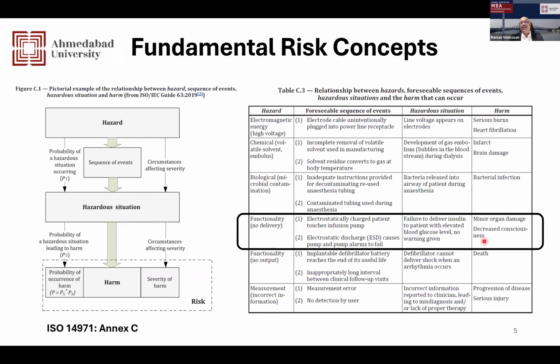And if that hazard somehow were to happen in a harm, the harm will probably be a minor organ damage or a decreased consciousness, which is a localized effect. But how it can happen, one of the potential modes, right? You can see some of the events that can happen. Maybe the patient is electrostatically charged due to the weather or clothes or whatever, and he touches the pump and the pump alarms fail and the pump also fails. And the hazardous situation is failure to deliver the insulin, right? So here you can see how a hazard, through a sequence of events, brings about a hazardous situation that results in harm, right? Now look at the next one.